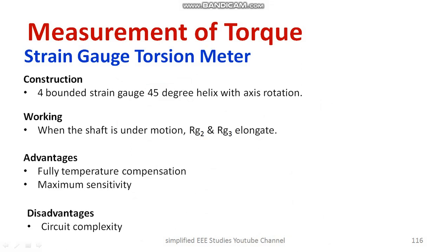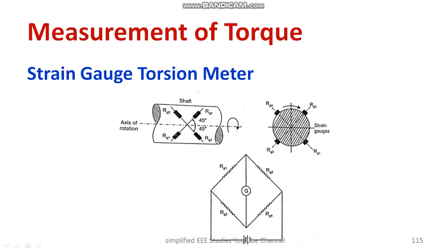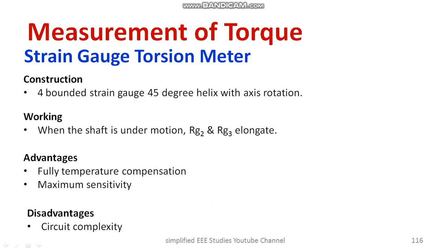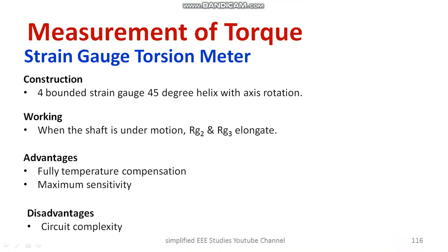When the shaft is in motion, RG2 or RG3 — any one of the resistive elements — can be measured as a variable. The torque is proportional to the change in resistance. The construction uses four bonded strain gauges arranged at a 45-degree helix with the axis of rotation. When the shaft is under motion, any one arm will elongate.